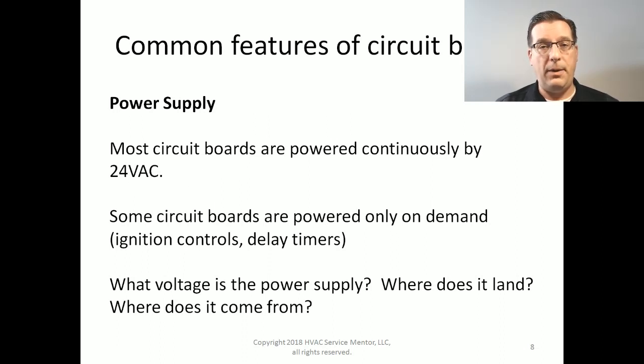Almost all control boards are powered by 24 volts AC in residential heating and cooling equipment. If you move on beyond residential heating equipment, you may start to find controls that have multiple power input voltages that they can run on. There are controls out there that will run on anything between like 18 volts up to 240 volts and anywhere in between. As long as you put some kind of power there, they're going to work. Those are becoming more common. However, residentially, pretty much everything is straight up 24 volts AC. Even if there's 240 volts or 120 volts landed on the board, that's probably not the power source. 24 volts AC is what powers them.